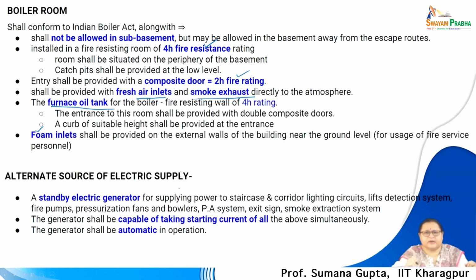Alternate source of electricity, as I have already told, all essential systems like the public address system, the fans and blowers, the pressurization system, the exit signs, the smoke extraction system, even the signages, the lift and staircase corridor lighting, should all be supported in case of a high rise building by the emergency electric supply or the alternate source of electric supply. The detection system, all detection systems, because the sprinkler system will not work if it is not supported. So, all automatic systems which are in operation should be supported with the generator or standby power, which will be necessary in case of an evacuation process.